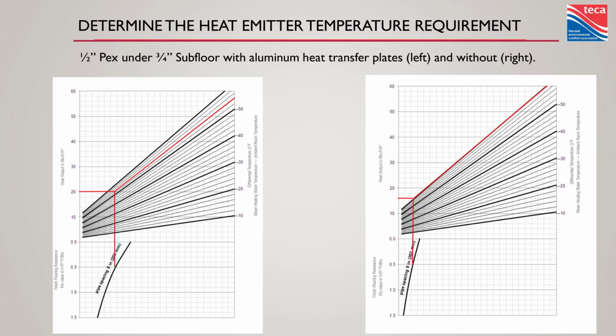Got some slides from some nice PEX people here comparing just tubing in the subfloor versus tubing with heat transfer plates in the subfloor. Exact same situation, our 0.5 floor covering. Let's take a look at without plates. I can get maybe 16, 18 BTU a square foot out of that if my water temperature is 60 degrees above my room temperature. That's pretty extreme.